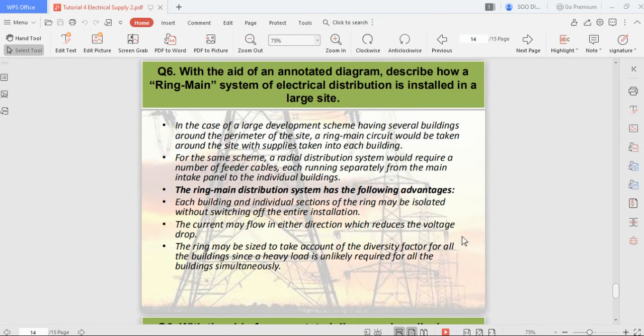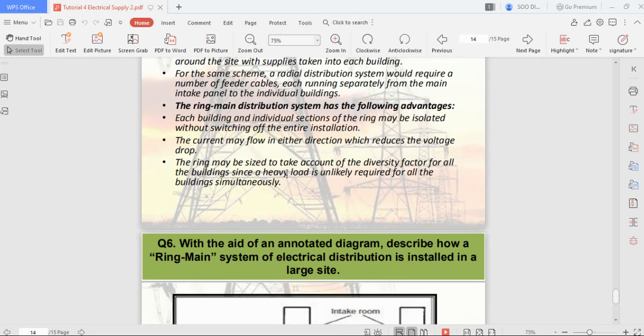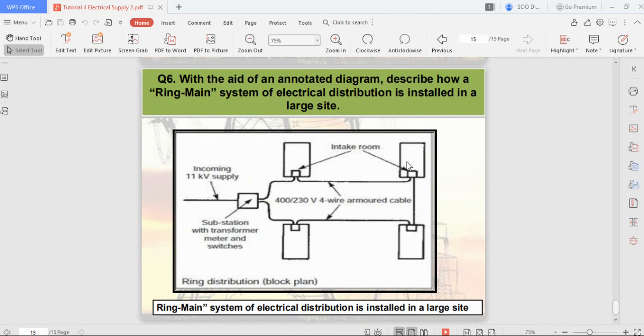And then you're able to reduce the voltage drop. Because you're building the system based on the area, you can reduce cost by sizing the cable accordingly. Since you're laying the cable underground, everything can be calculated, and once the correct appropriate size is obtained, we can cut costs by planting the correct size. That means we do not oversize the cable — we do not give a cable which can transmit 5 kilovolts when we just want a cable sized appropriately for the transmission needed in that large area.